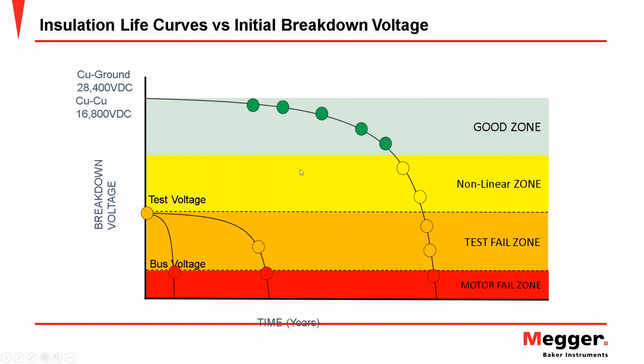And all we're doing is leveraging that high voltage capability of the insulation system to evaluate its change, right? So as it begins to show a nonlinear characteristic, for example, then we get indications. If I'm just doing low voltage testing, if I'm just doing Megger testing, I'm down here around the motor fail zone. By the time I have indications that the insulation is beginning to weaken, it's probably too late for us to even take action, if we even find it at all.